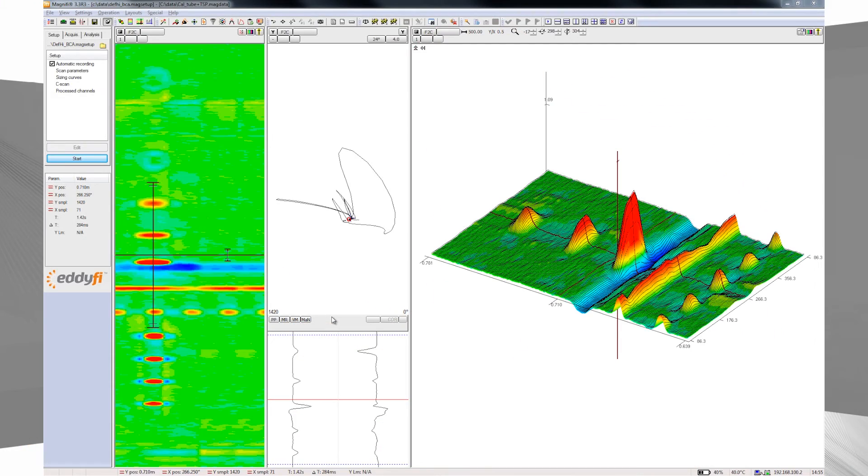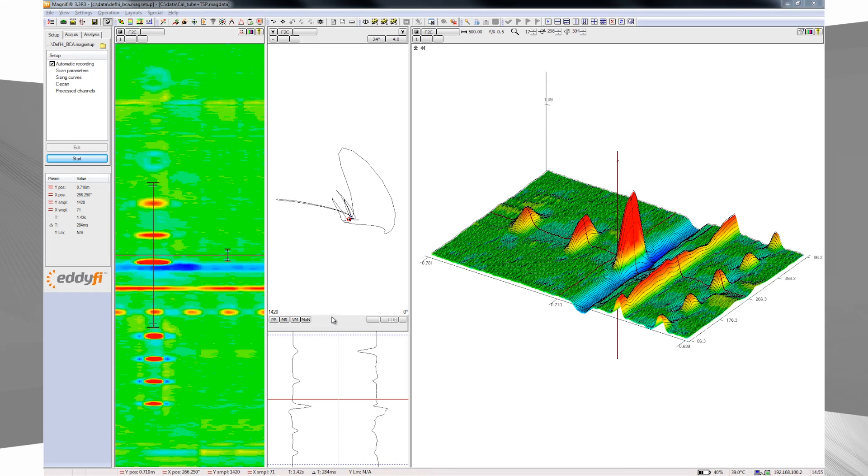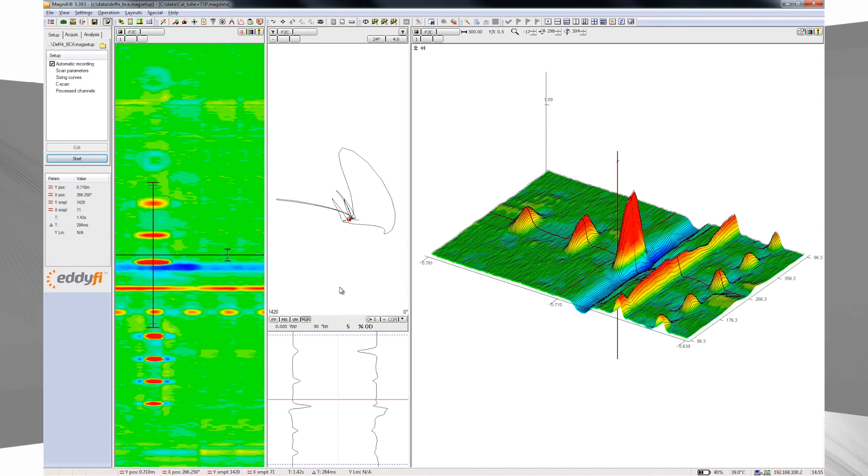You can see that the ferromagnetic interference induces a strong negative response, but the defect remains visible. The C-scan clearly shows the circumferential extent of the crack and the phase is used to assess the depth.